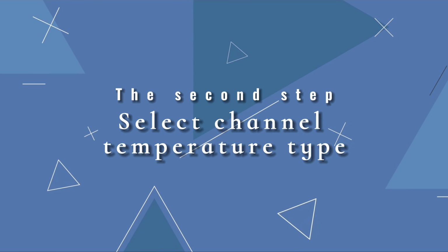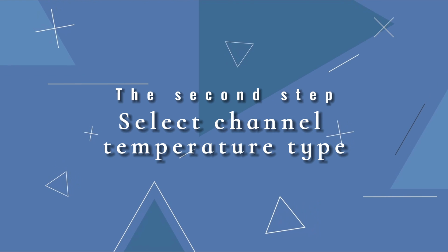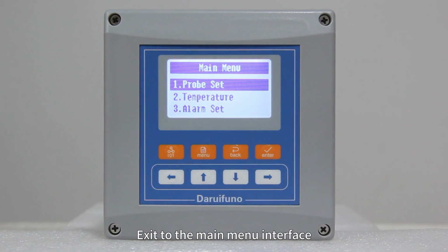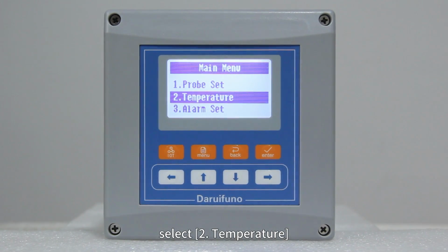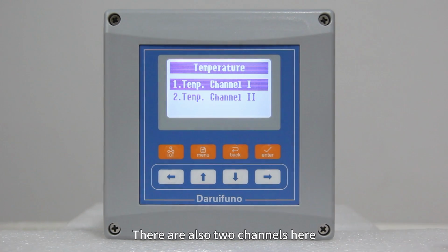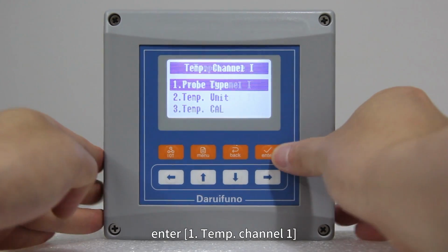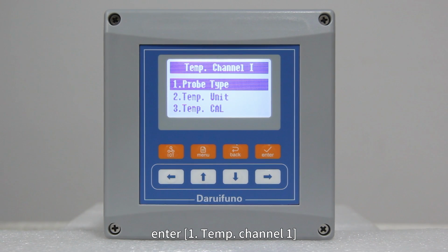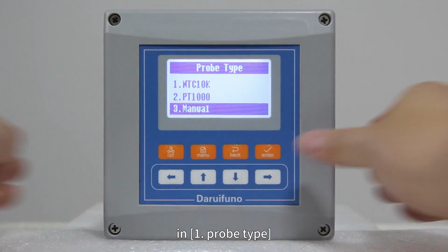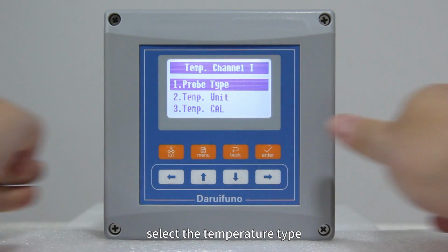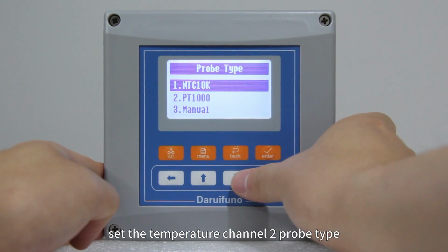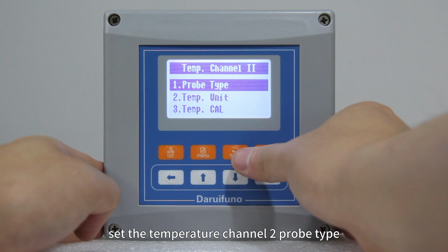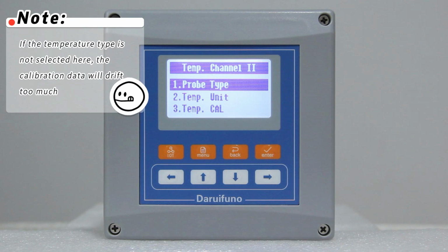The second step, select channel temperature type. Exit to the main menu interface. Select Second, Temperature. There are also two channels here. Enter First, Temp Channel 1. In First, Probe Type, select the temperature type. In the same way, set the temperature channel 2 probe type. Note, if the temperature type is not selected here, the calibration data will drift too much.